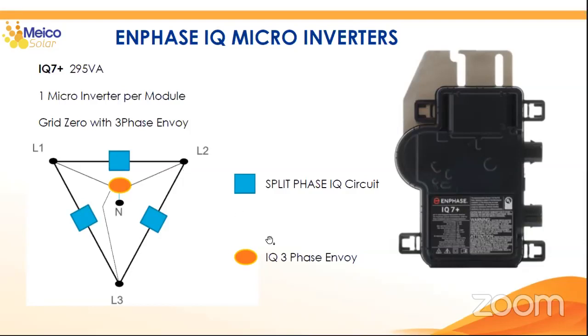Then you put the IQ, the three-phase envoy, in the middle, and you have reference of the three lines and the neutral. This is the way you can install ENPHASE in a three-phase low voltage connection and grid tied type.